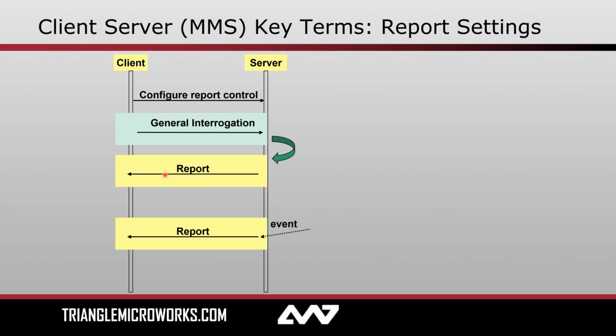Now, this is in contrast to event-driven. In this next example, the event could be a data change, something in that report changed, or it could be the quality of something in that report changed. In either case, the report is automatically generated by the server and published up to the client. In kind of a similar vein, we have cyclic reporting. In this case, we're not looking for data to specifically change. We're only waiting for a timer to expire. And after that timer expires, data is sent up from the server to the client. Now, one thing I should note in these event-driven approaches, only the data that changes is packaged in the report, whereas with the general interrogation, for example, all the data in the data set is sent. So using event-driven, aside from the fact that you just won't miss any data changes, is also a little bit lighter weight on the wire.